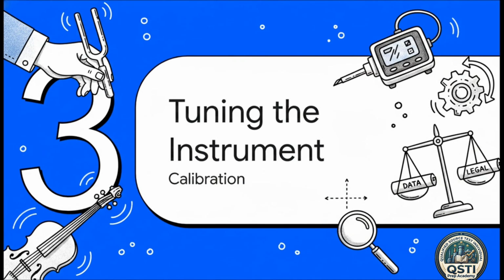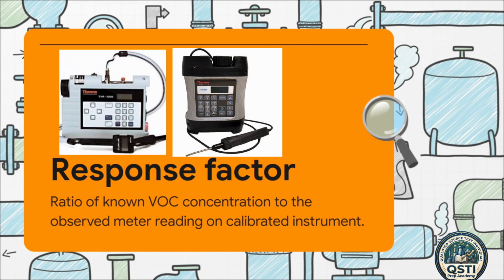Which brings us to Section 3, tuning the instrument through calibration. Just like a musician meticulously tuning up before a high-stakes concert, an inspector has to calibrate their gear. Since the data collected here is legally binding, the machine's accuracy is totally non-negotiable. We have to make sure our instrument correctly translates the invisible gas it smells into accurate, actionable data. And it does this using what's known as a response factor. Essentially, it's just the ratio between the actual known concentration of the gas in the air and the number the machine spits out on its screen.